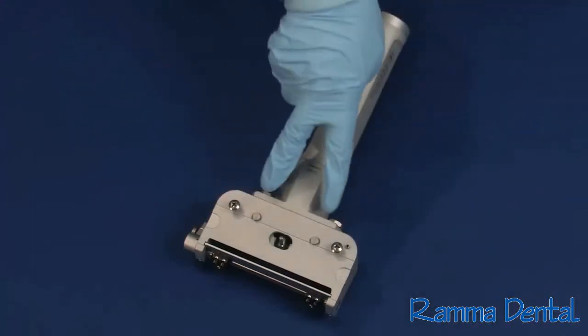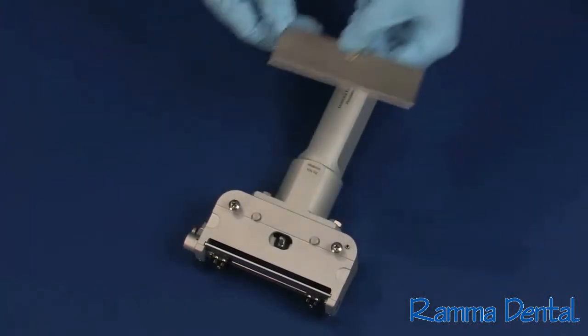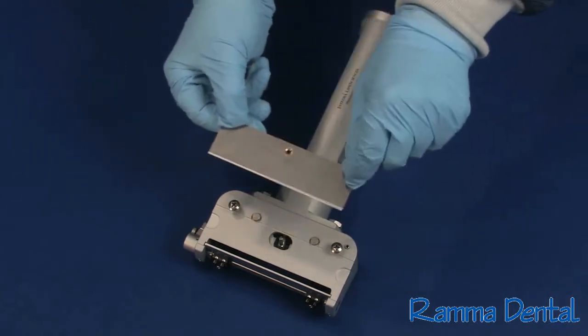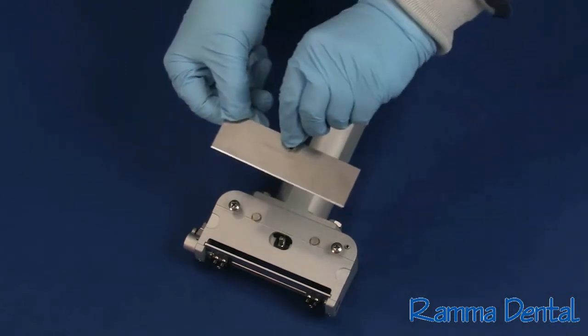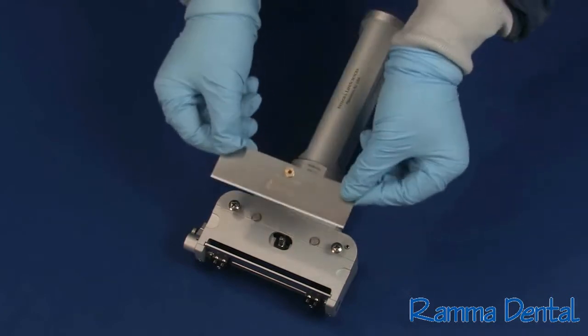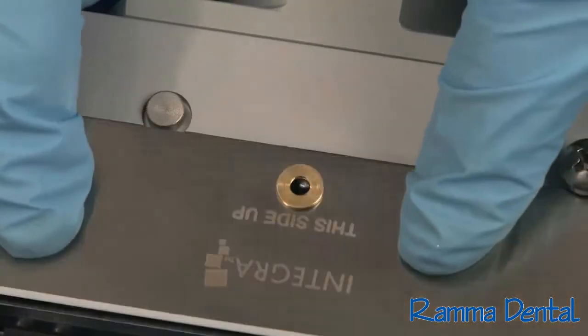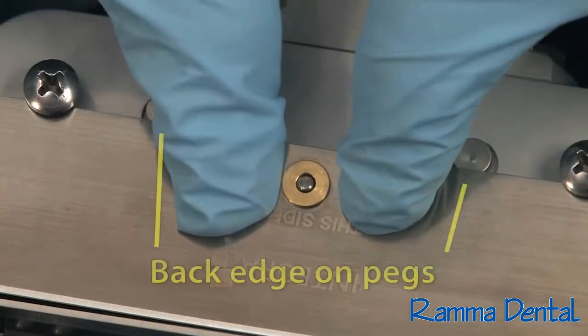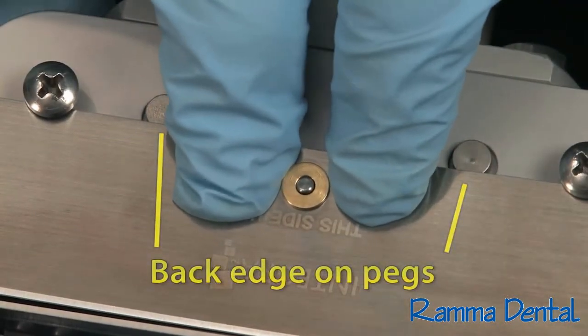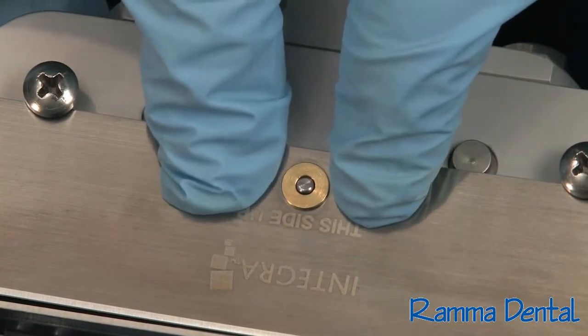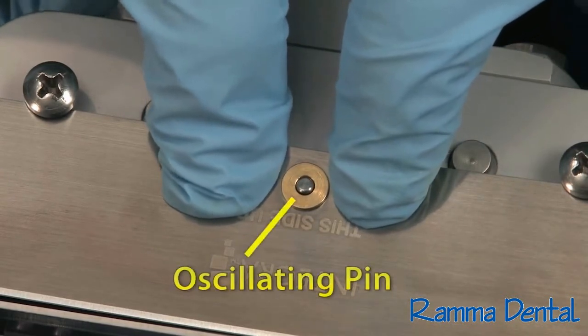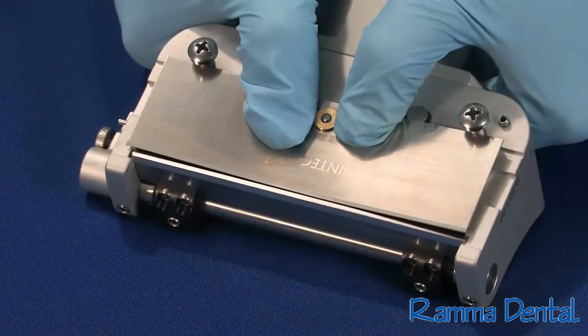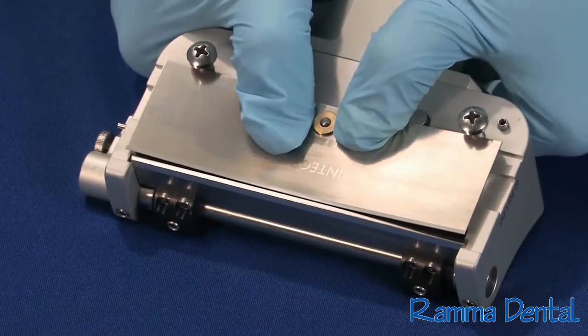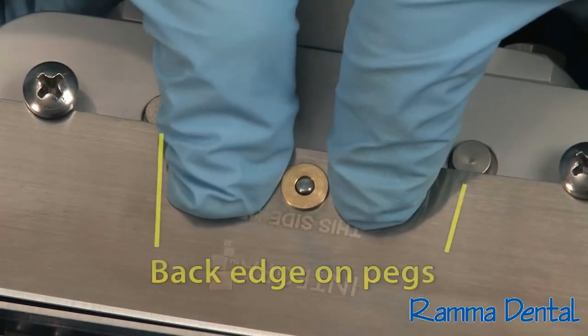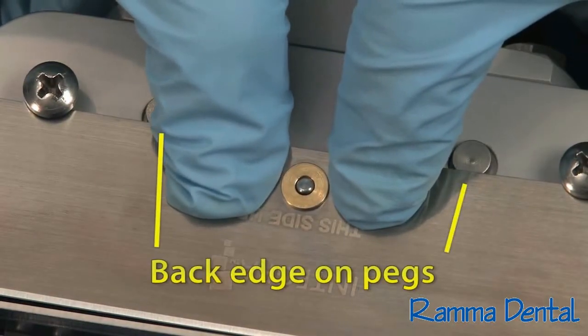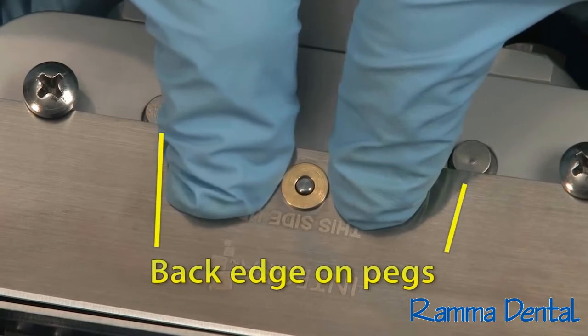Note that the dermatome has 2 pegs for holding the blade in place. Prior to placement, the blade should be given a very thin coat of sterile mineral oil on the unmarked underside. With the Integra logo up, center the blade hole over the oscillating pin with the back portion of the blade resting on the 2 pegs. At this point, you should be able to press down with your thumbs on either side of the blade and observe the oscillating pin passing through the blade hole as the blade bends slightly. Note that while doing this, the back portion of the blade continues to rest on the pegs. This is the starting position for installing the blade.